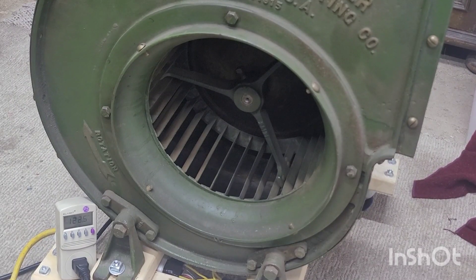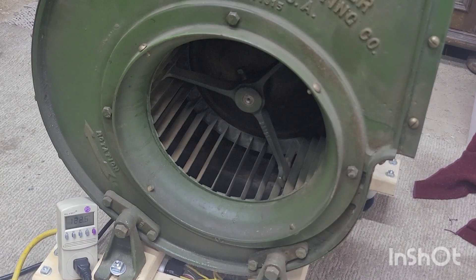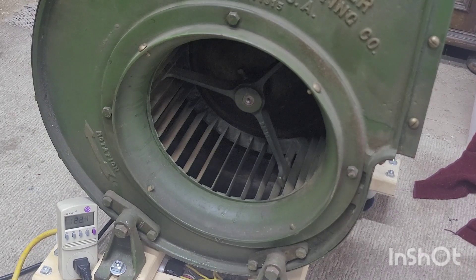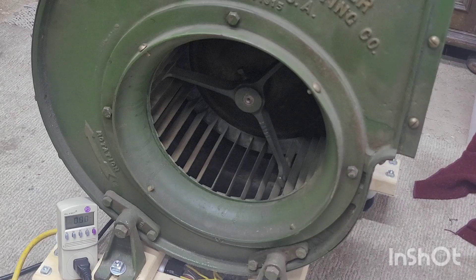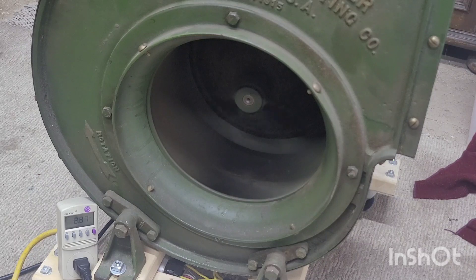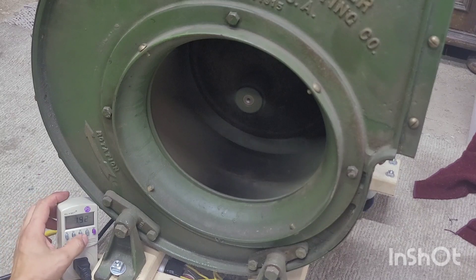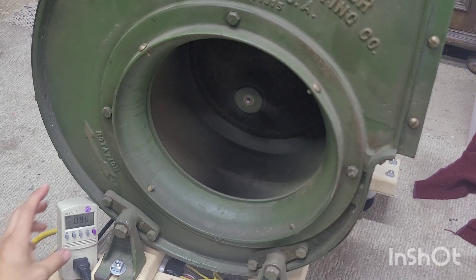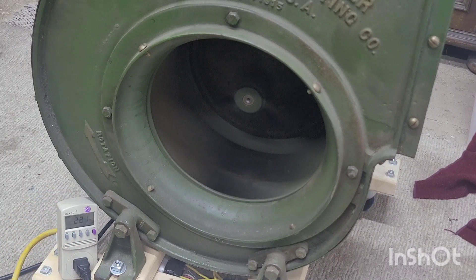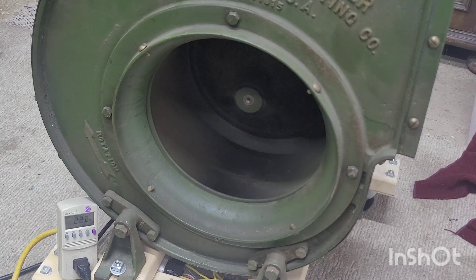Hopefully you'll be able to see that meter. Right now we've got 122.5 volts coming in. I'm going to switch this over to current and we're going to start this up. The first time you're going to see this start is with the start capacitor. So here we go. You can see I'm only drawing 1.92 amps and a power factor of 0.95, and we're drawing 220 watts.